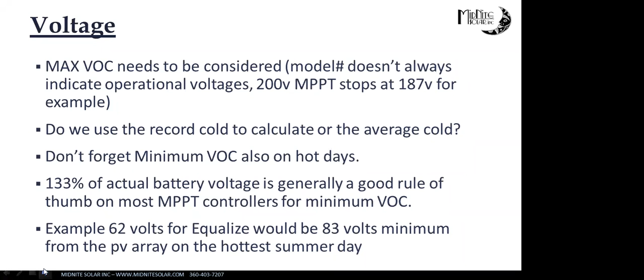So a lot like a solar module, a battery is a little bit backwards. As a battery falls below that standard test condition, or that 70-ish degrees Fahrenheit, 25 degrees C, it needs a little higher voltage to properly charge. It needs to be pushed a little harder. And if it's above that and it's hot, it needs a little less. It doesn't need to be pushed quite so hard. So all your common charge controllers will do that for you, but that is sometimes alarming to new customers when they see their voltage going above their set point and they're not sure why.